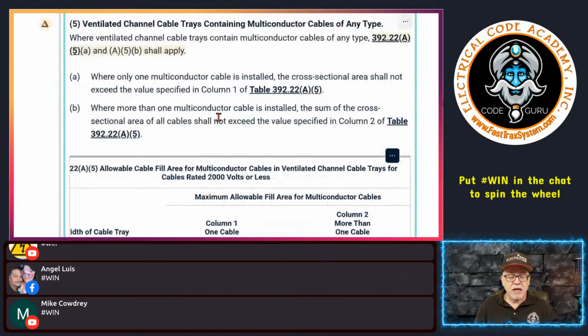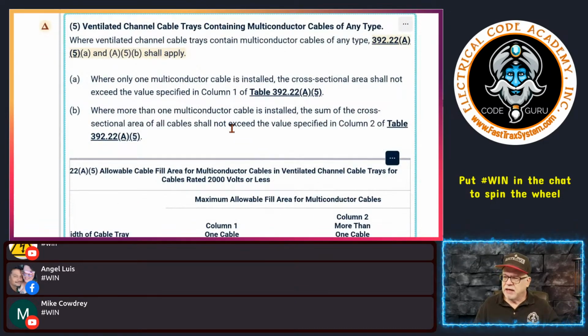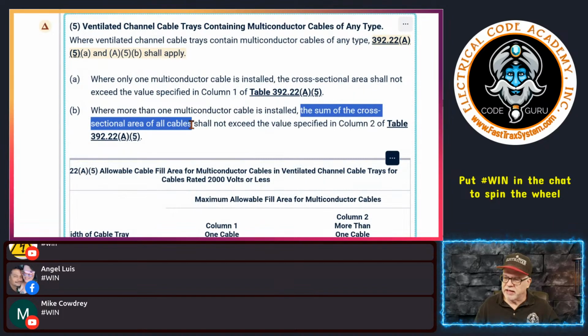Now, where do you get this value? This is a call, again, like I got a call last night. When it says the sum of the cross-sectional area of the cables, that is why I gave you that Math Is Fun. Go back and watch that in episode 2 of this cable tray sizing, because there I gave you a URL. You can freeze the screen and write it down. That's how you basically, if it's a cable, find the area of it. We're going to need the diameter, or circumference, but the easiest one is to find the diameter of the cable. You get that from the manufacturer. I guess you could measure it yourself. And then you use the formula to calculate the area, and that would be your area.